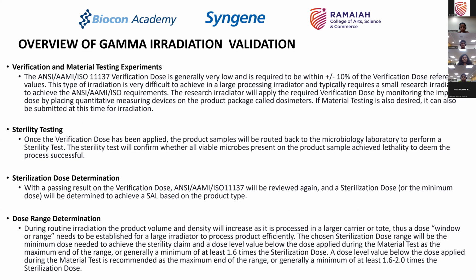Okay. Now, during routine irradiation, the product volume and density will increase as it is processed in a large carrier or tote. A dose window or range needs to be established for a large irradiator to process the product effectively. The chosen sterilization dose range will be the minimum dose needed to achieve the sterility claim, and a dose level value below the dose applied for the material test as the maximum end of the range, or generally a minimum of at least 1.6 to 2 times the sterilization dose.